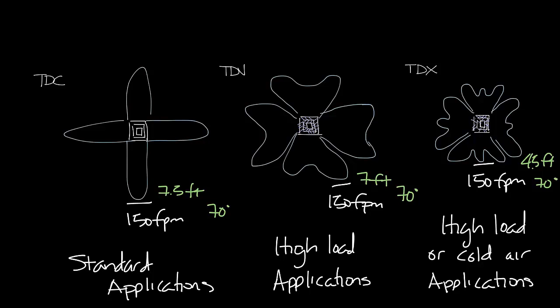One thing to remember though is that the higher mixing could cause additional sound. So depending on your airflow the TDX could be three or four NC higher than the TDC or TDV.